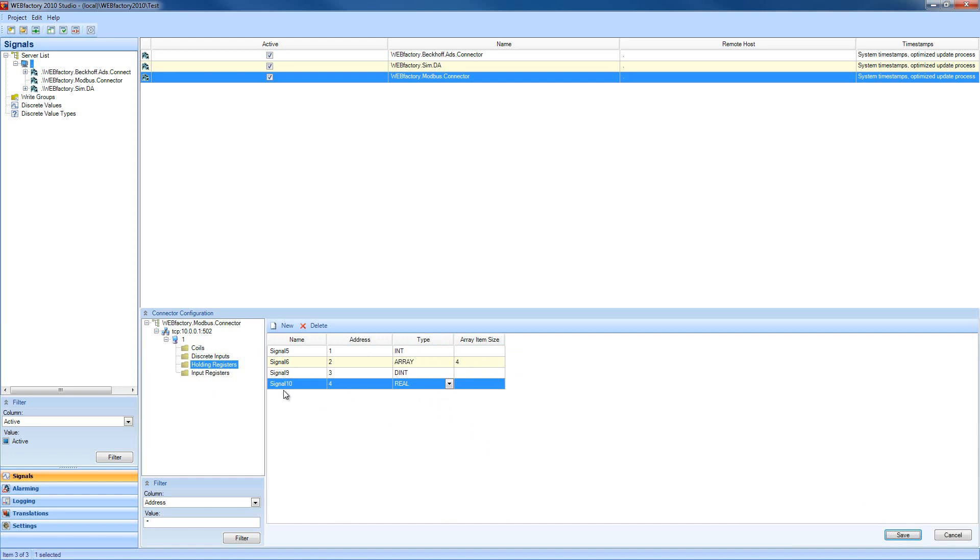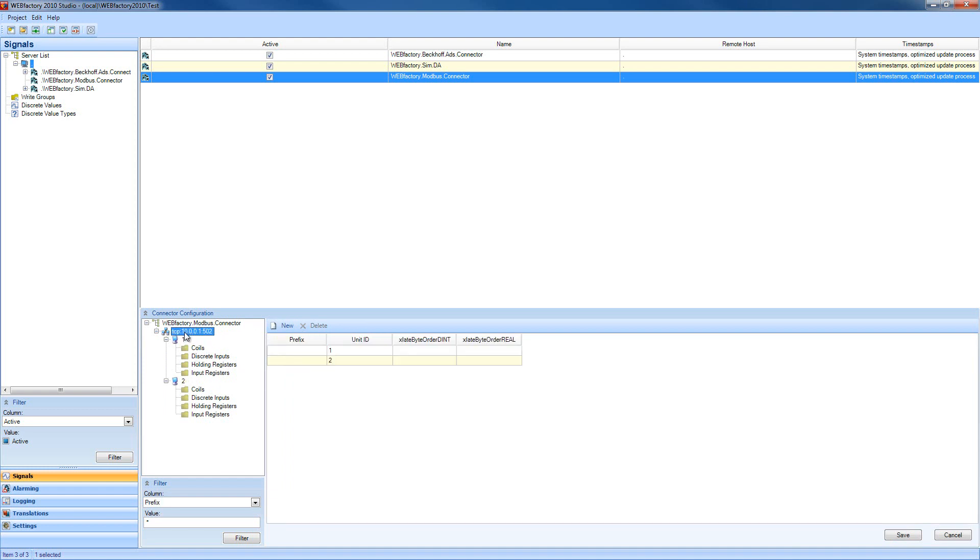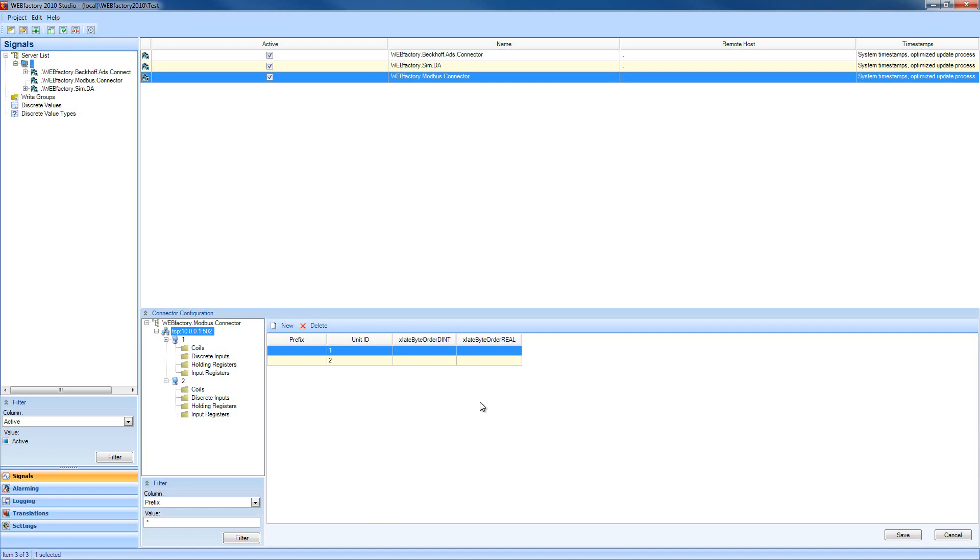I'm going to save the configuration and proceed to creating another Modbus substation to demonstrate how our substations are linked to our main Modbus device. If we select our Modbus device, we can define different prefixes for each substation. These prefixes will be imported as signal prefixes in WebFactory 2010 when we browse the connector. We have the unit IDs of these substations, which are unique identification numbers, and we have options for xlate byte order double integer and xlate byte order real. We can use these to define the order of the high byte and low byte. In the usual Modbus setup, these two options have the same value.